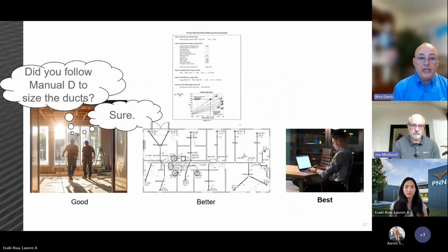The easy way, you could ask. A better way, you could ask for a duct sketch, and to tell you the truth, if it was the previous duct sketch, that would be fine as long as it was based on the loads and the friction rate worksheet, which is illustrated above. If you ask for those two documents, again, like the performance data, it's an indication that the procedure was done correctly. The best way would be to have someone that can look at the plans and the friction rate worksheet and assess if the ducts were actually sized correctly.